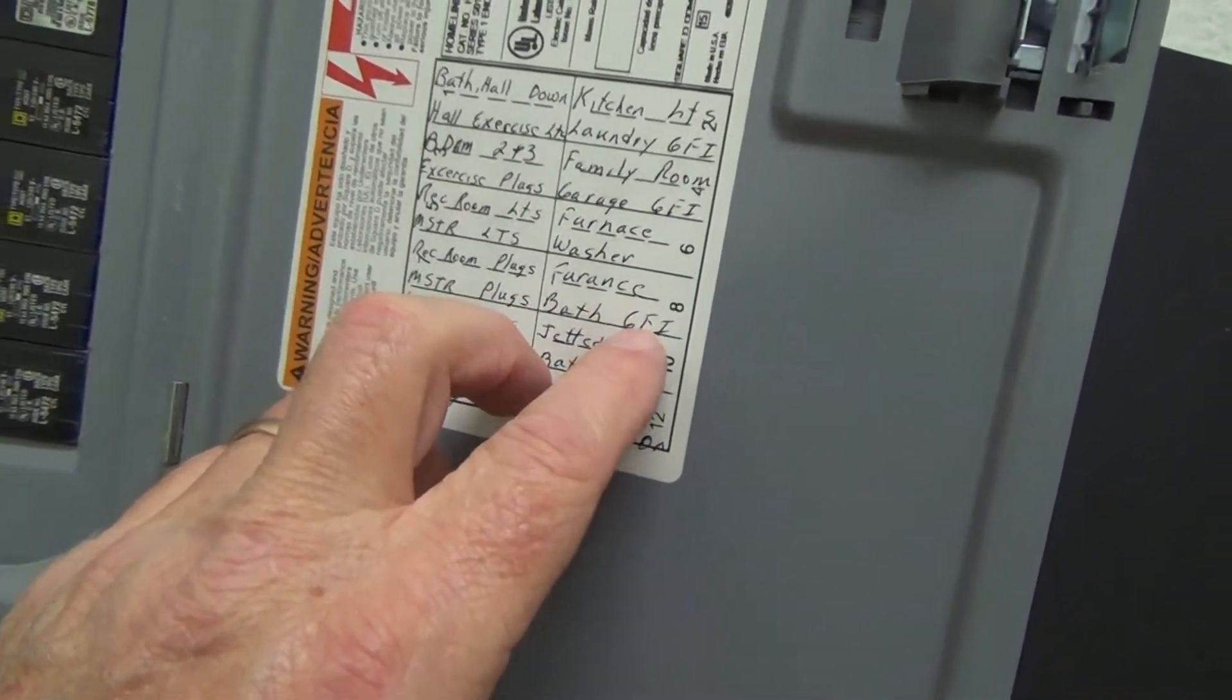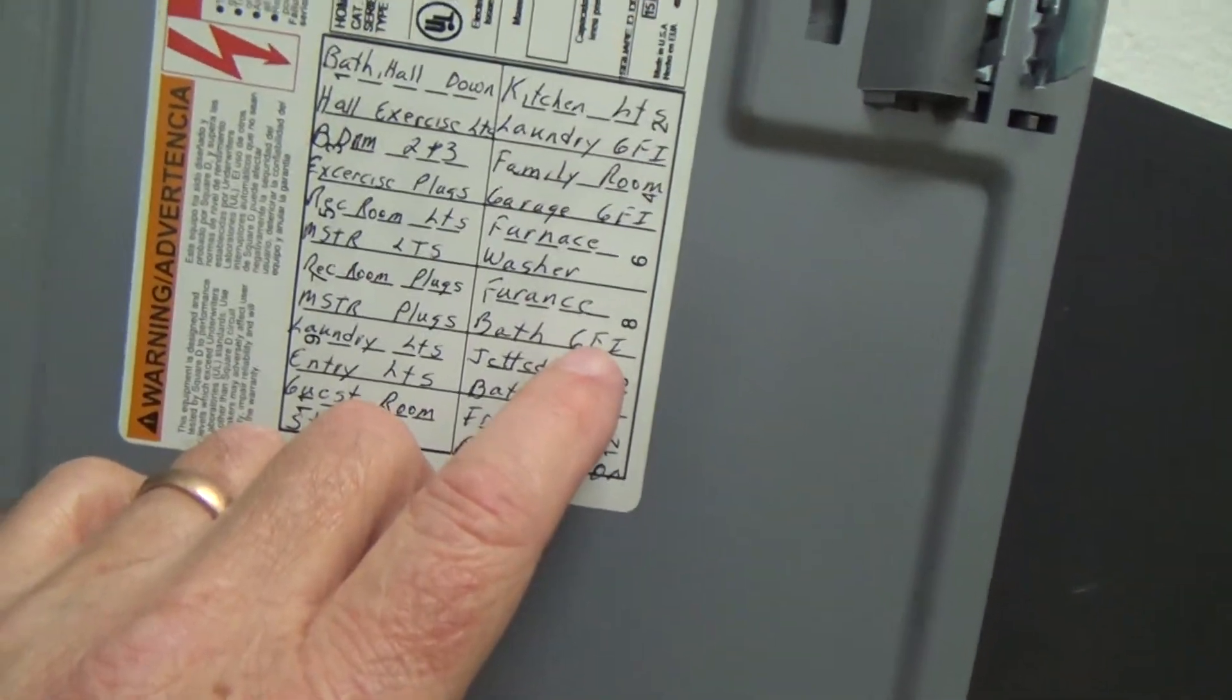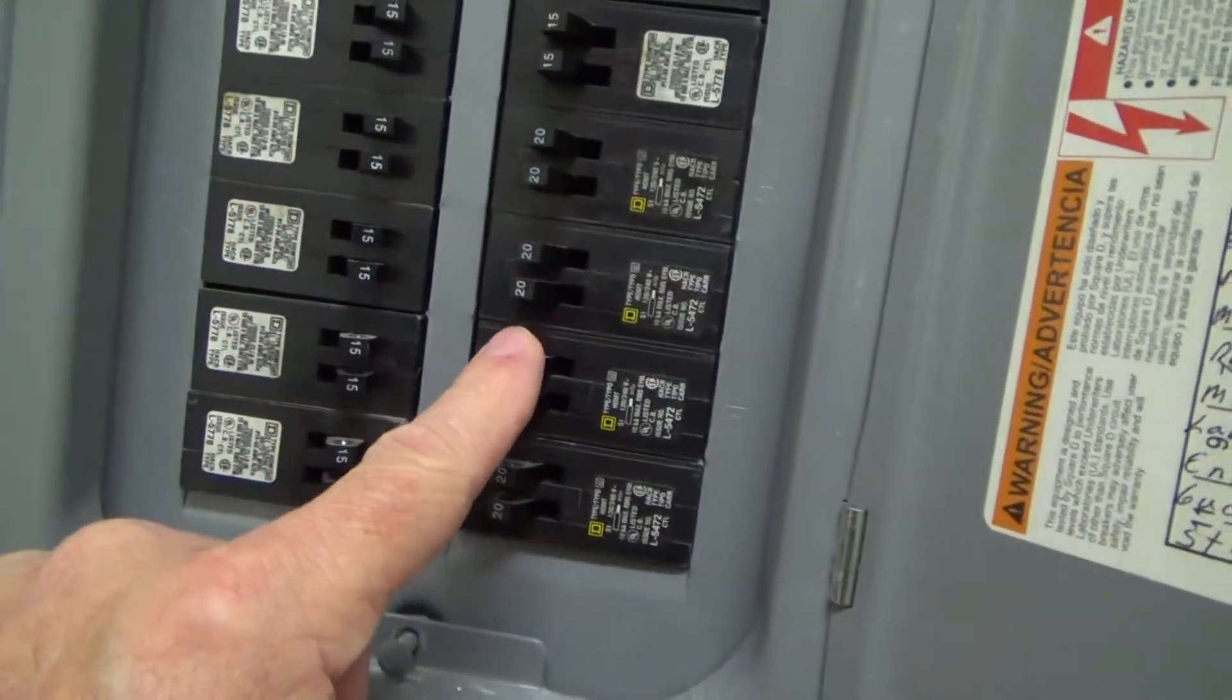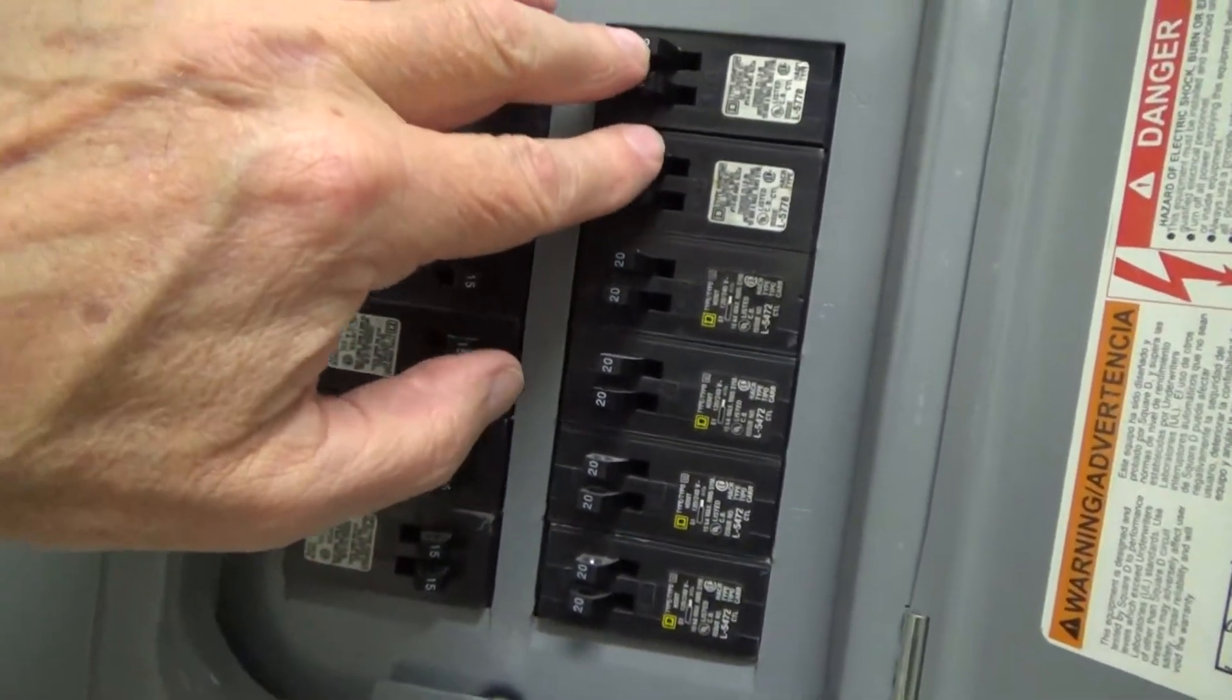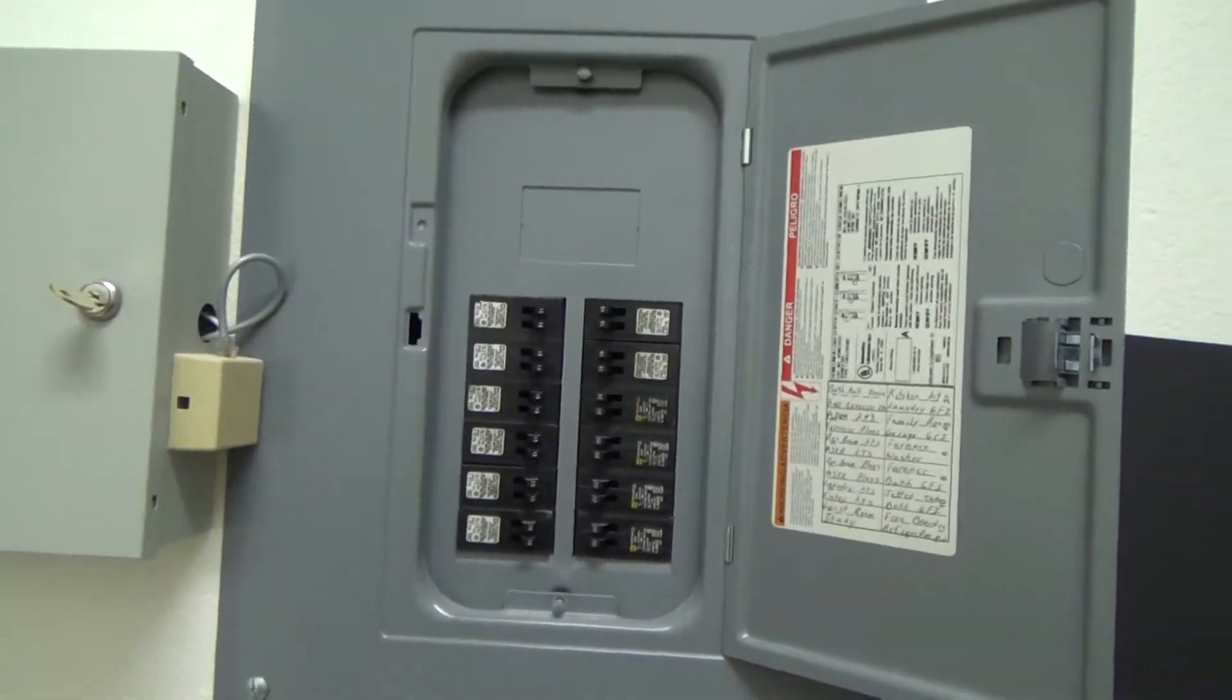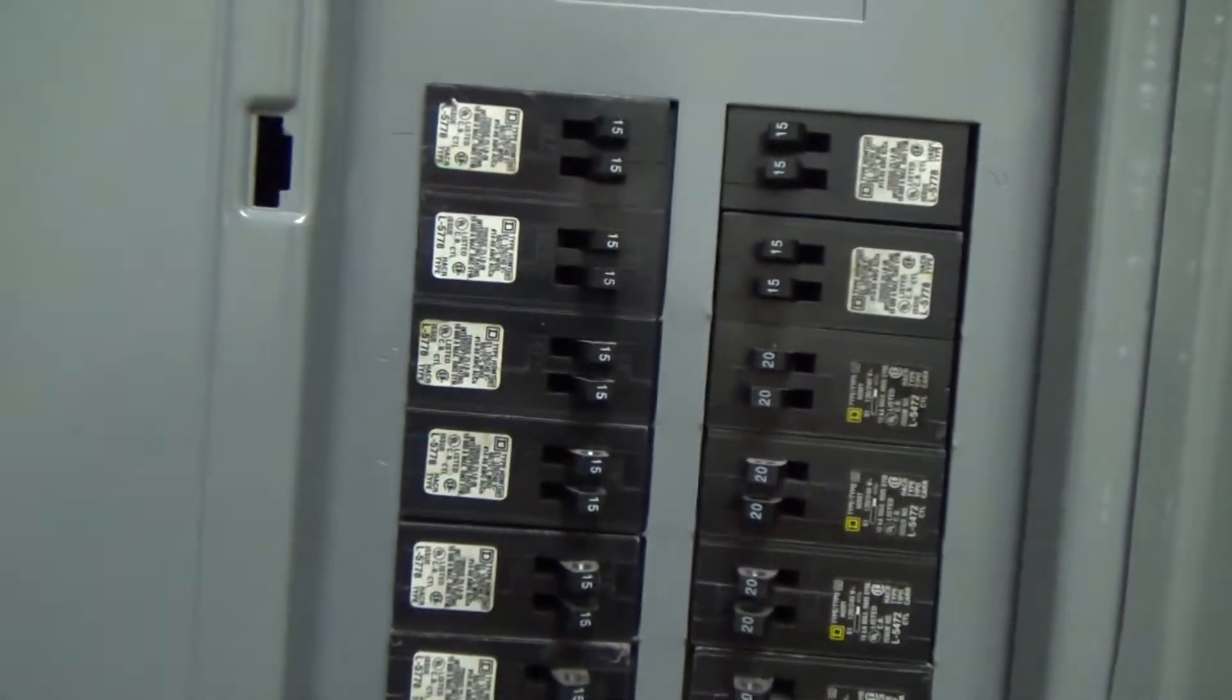If you've got one duplex, you might have a heating iron in one and you might have a blow dryer in another. And so that's why they put those on 20 amp circuits. So we know for all the bedrooms, all the electrical outlets and all the light switches are in 15 amp circuits for this particular house. That tells me that I can use 14 gauge wire to hook up the ceiling fan.